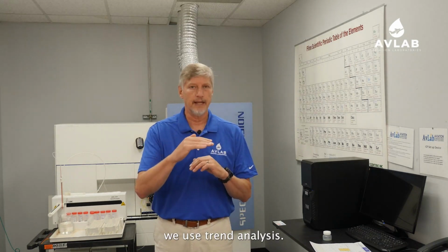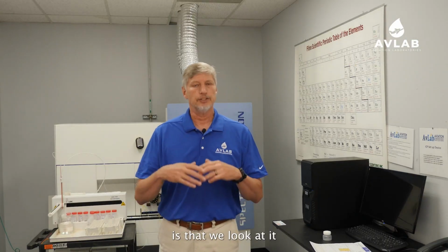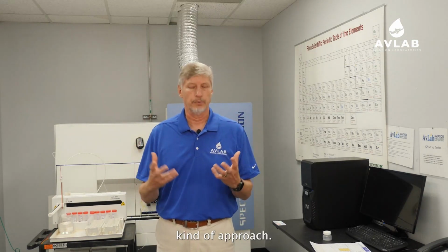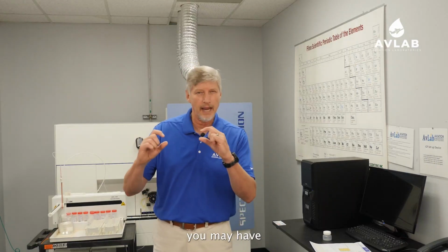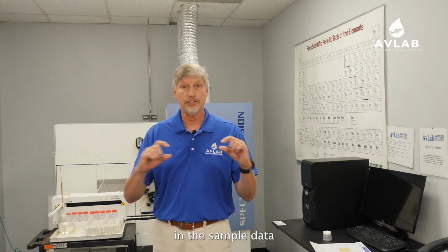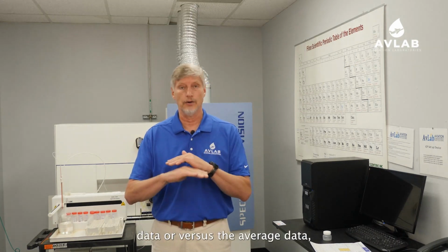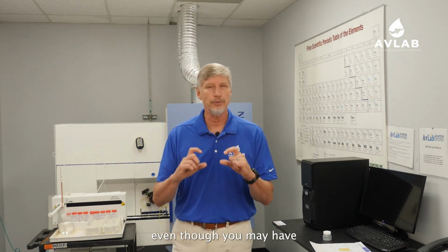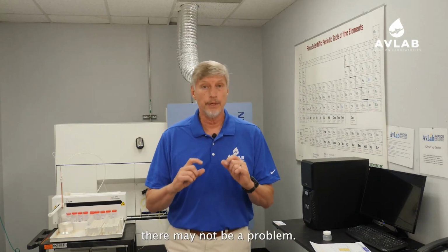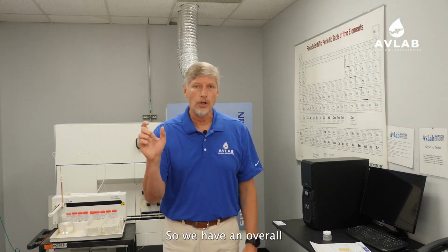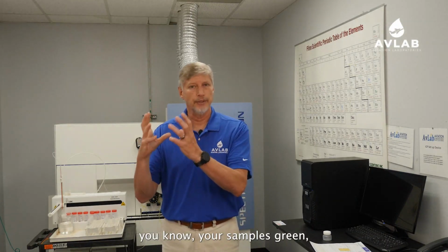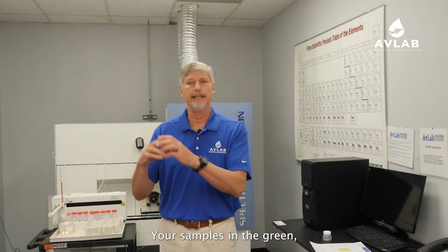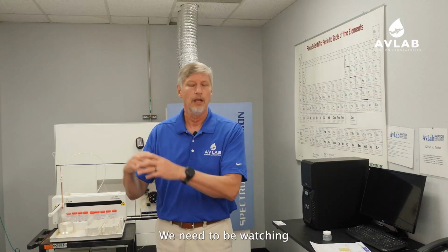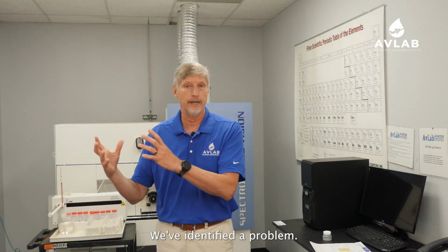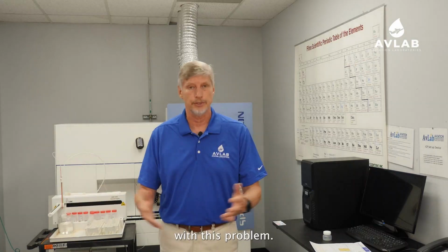So we use comparative statistics. We use trend analysis. The third thing we do is that we look at it more of a holistic kind of approach. We say, even though you may have these slight anomalies in the sample data that you have versus previous data or versus the average data, they may not be a problem. So we have an overall, we call it an alarm meter, that tells you your sample's green, sort of like a stoplight. Your sample's in the green, it's yellow, it's a caution, we need to be watching, or it's red. We've got a problem, we've identified a problem, you need to proactively deal with this problem.